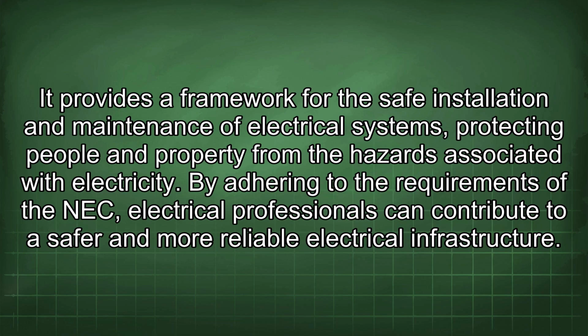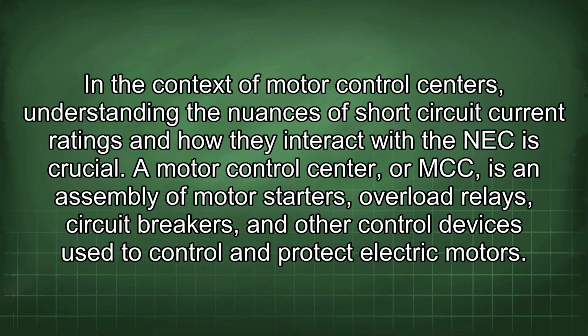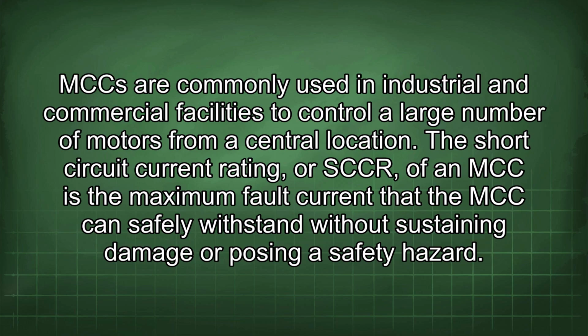reliable electrical infrastructure. In the context of motor control centers, understanding the nuances of short-circuit current ratings and how they interact with the NEC is crucial. A motor control center, or MCC, is an assembly of motor starters, overload relays, circuit breakers, and other control devices used to control and protect electric motors. MCC are commonly used in industrial and commercial facilities to control a large number of motors from a central location. The short-circuit current rating, or SCCR, of an MCC is the maximum fault current that the MCC can safely withstand without sustaining damage or posing a safety hazard.